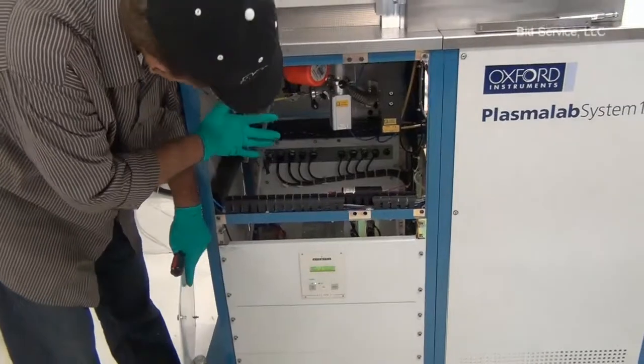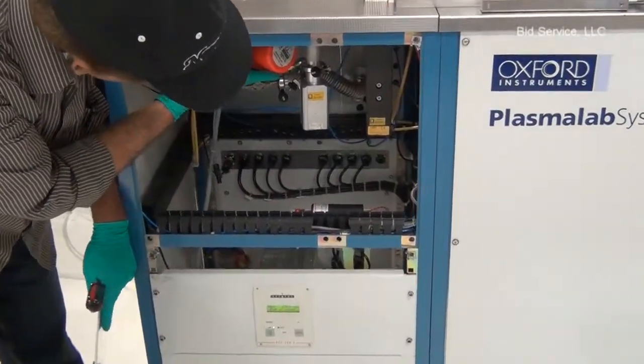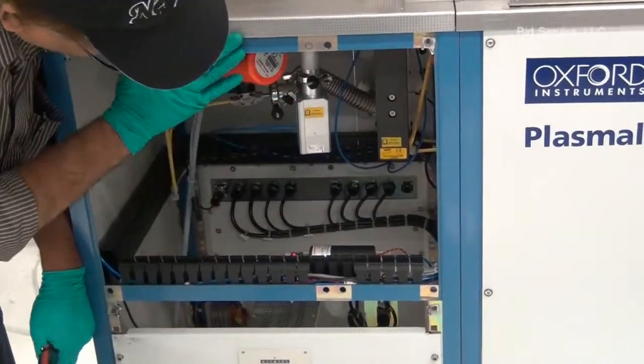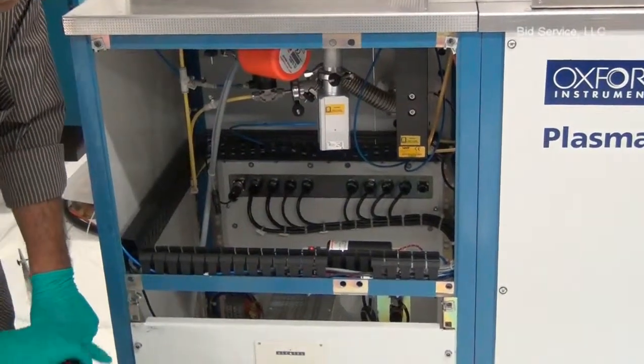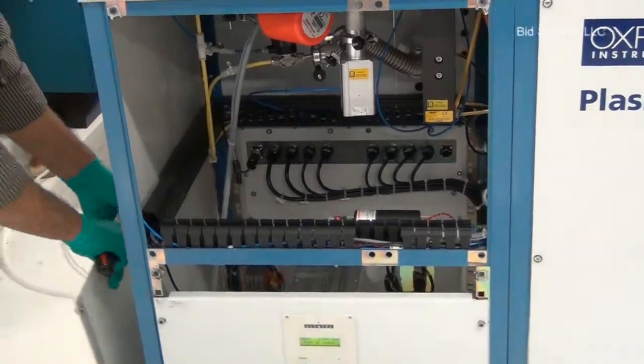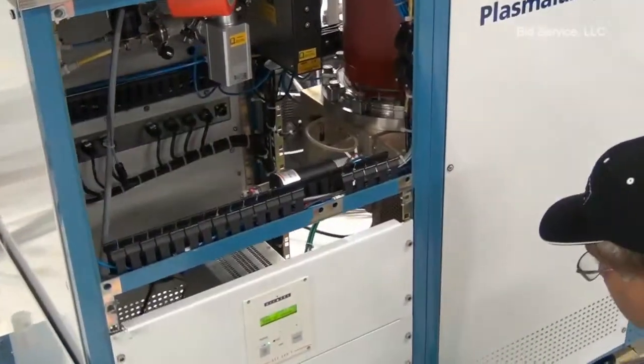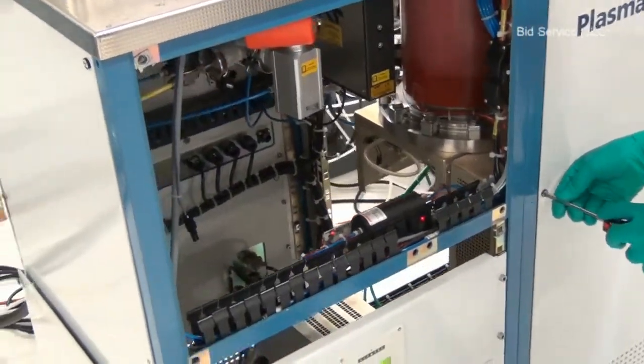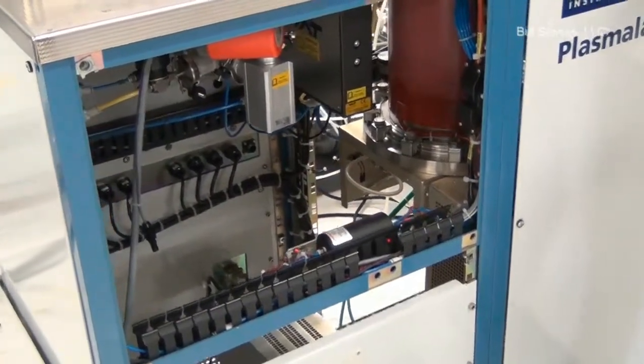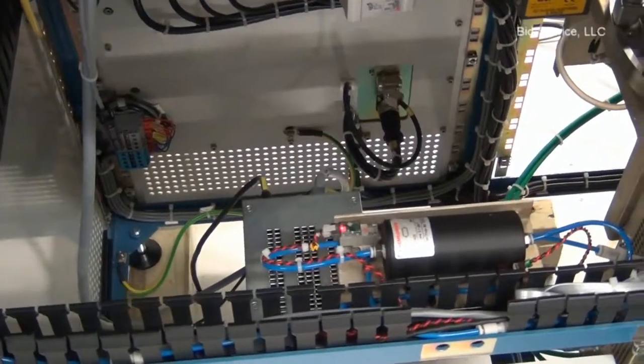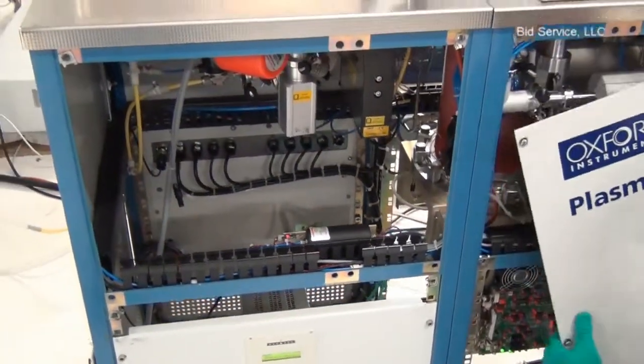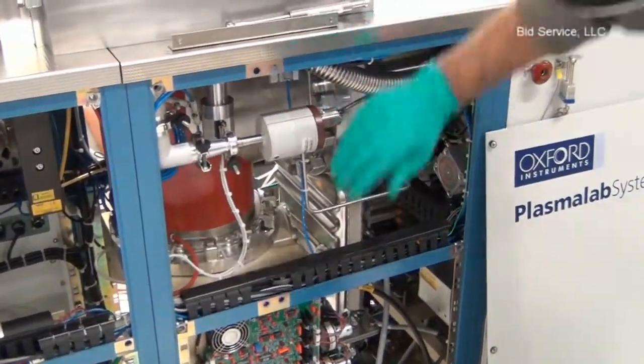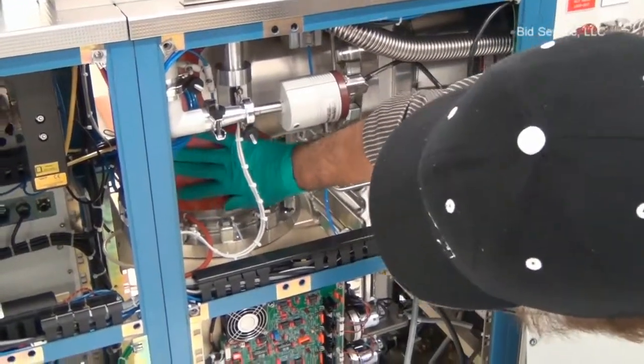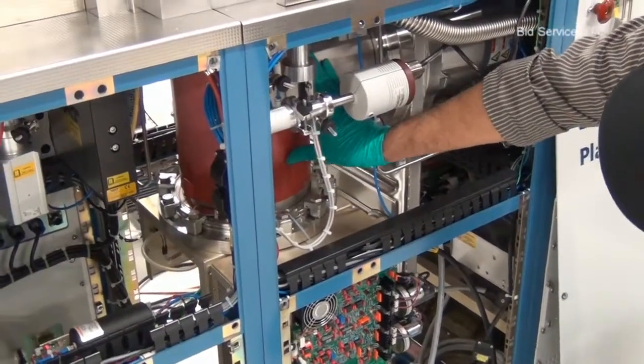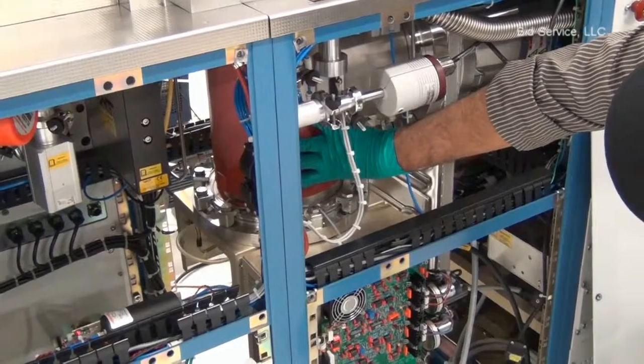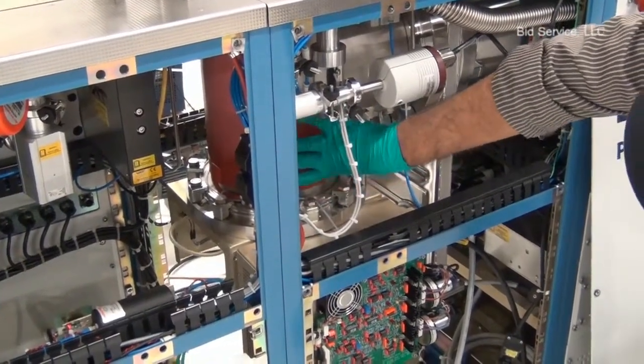So, underneath the load lock chamber, we have the high vacuum sensor, and the isolation valve between the load lock chamber and the main chamber. Underneath the main chamber, this red jacket is the heater for the vacuum area. This column, if we heat it, it will eliminate the outgassing of the walls.